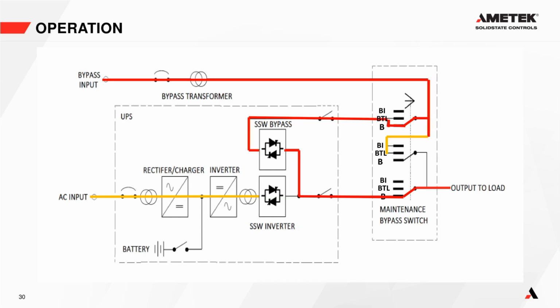And the main reason for that is somebody has to physically press the bypass to load button. And if somebody has pressed the bypass to load button, that means they are probably starting a switching sequence to put the system into maintenance operation and do some maintenance on the UPS. So our principle is, if somebody has told it to go to bypass, then there's a reason for it. So therefore, if we had an automatic switch back to the inverter static switch, if the bypass failed, then that switching procedure would be confused, it would be messed up, and could, in theory, put somebody in danger if you're going through a lockout tagout process.